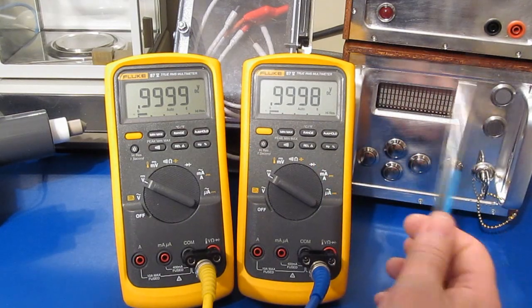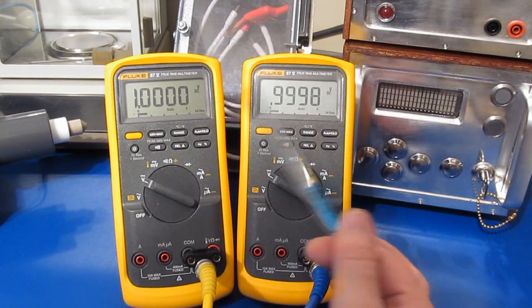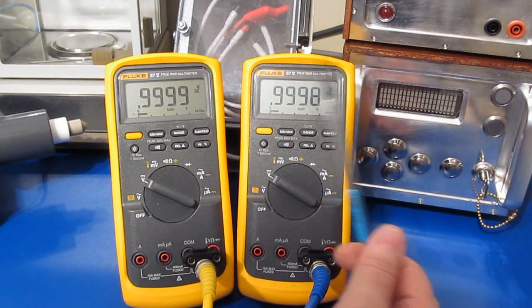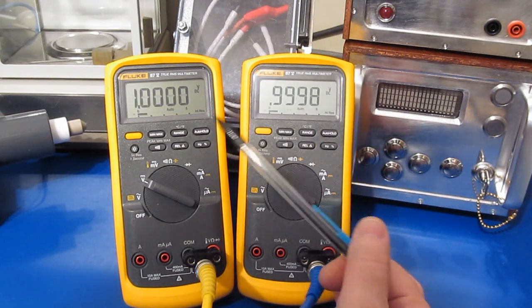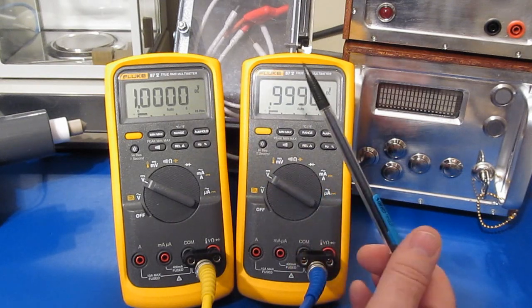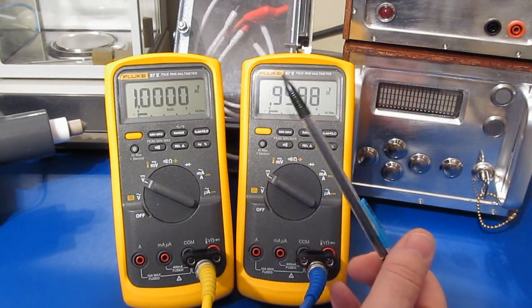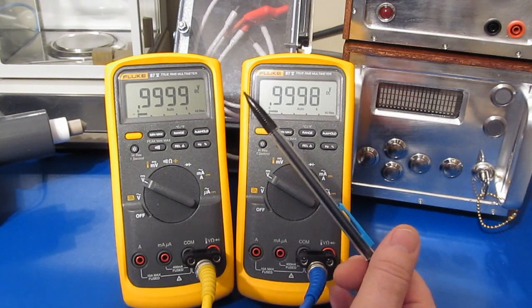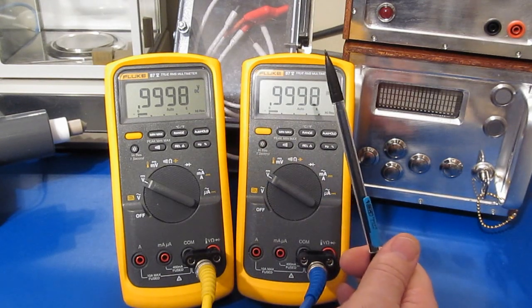Again, this has nothing to do with safety. If you're trying to determine if a meter is robust before buying it, what you're looking for is whether the meter has passed the IEC 61326 standard. That's the EMC standard, not the safety standard.